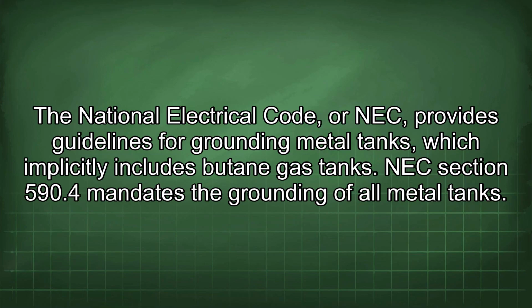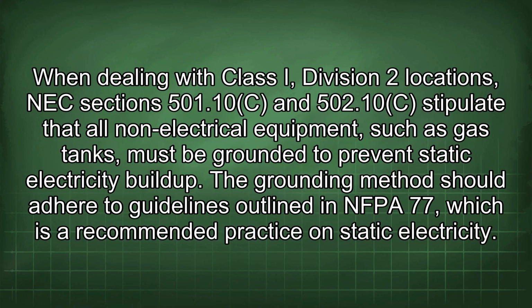The National Electrical Code, or NEC, provides guidelines for grounding metal tanks, which implicitly includes butane gas tanks. NEC Section 590.4 mandates the grounding of all metal tanks. When dealing with Class I, Division II locations, NEC Sections 501.10c and 502.10c stipulate that all non-electrical equipment, such as gas tanks, must be grounded to prevent static electricity buildup.